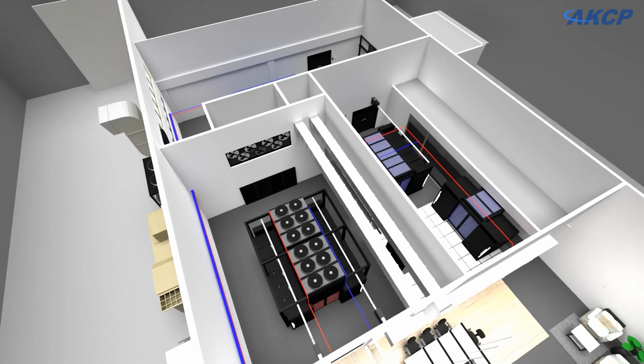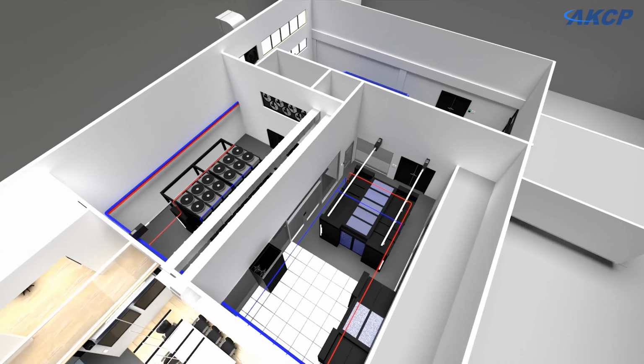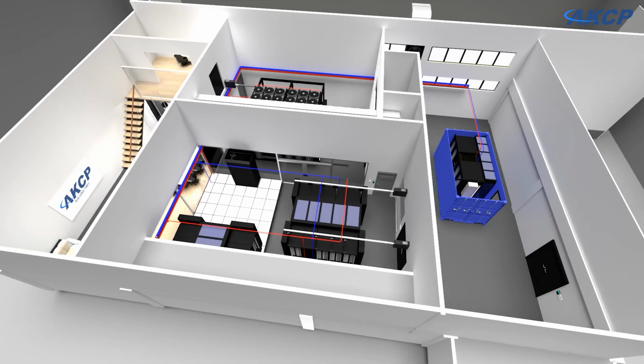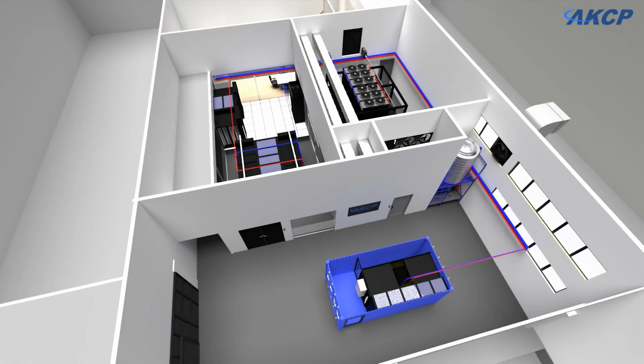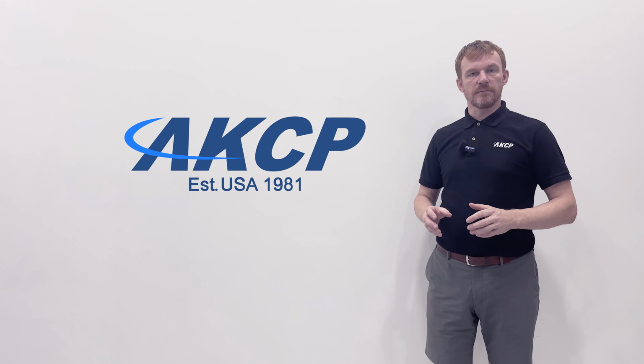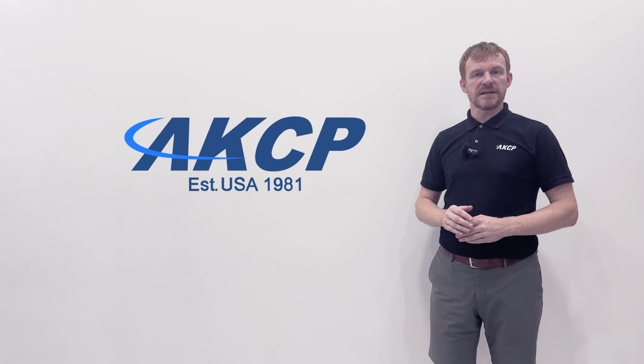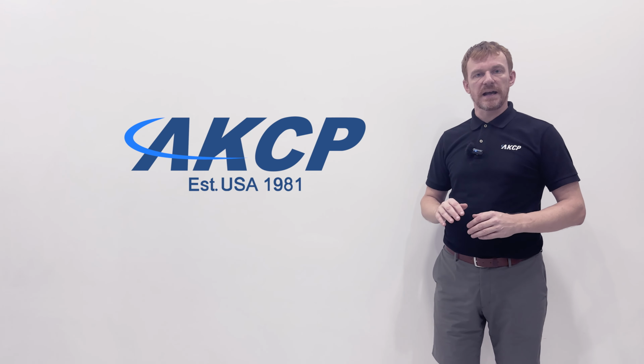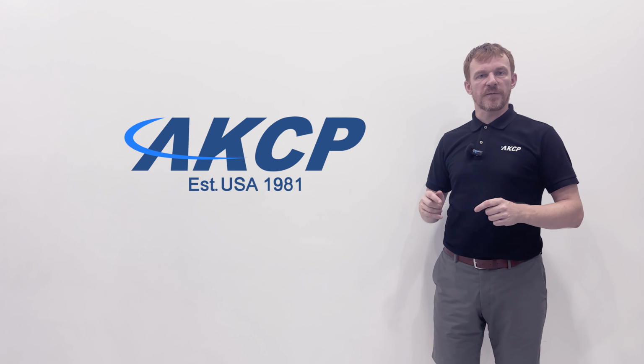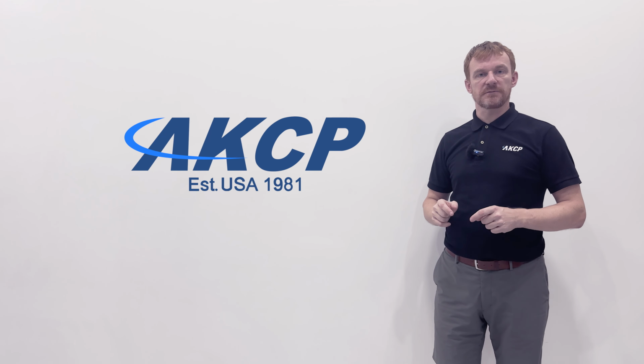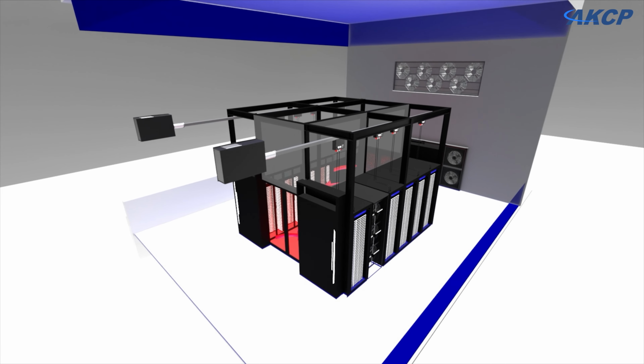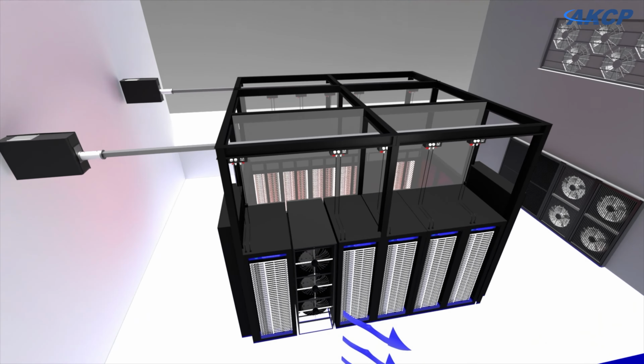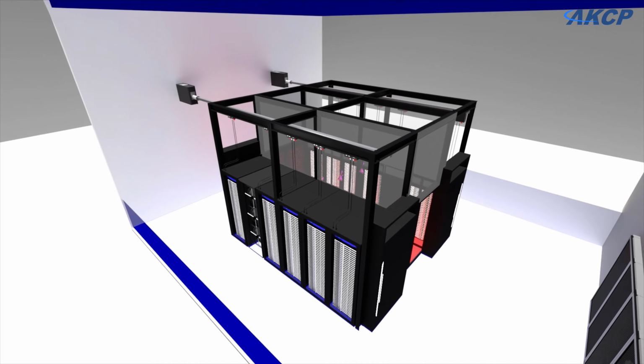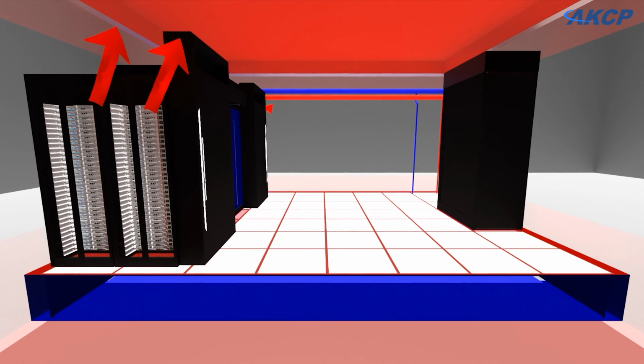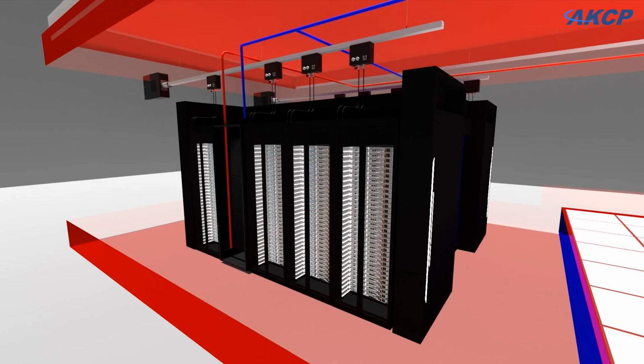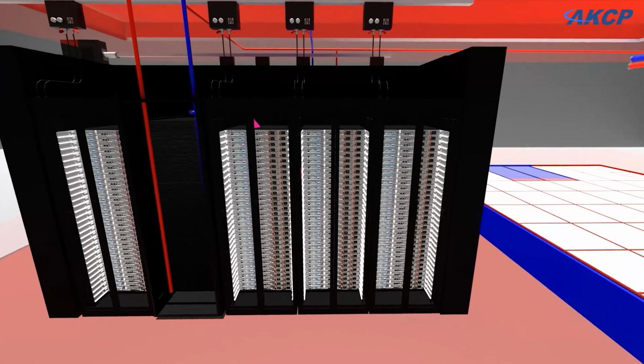What you can see on the screen is our 3D representation of the test data center under construction. We've got hot aisle containment, cold aisle containment, fan walls, and at the moment we're doing construction of a steel structure to support our overhead rooftop heat exchangers. We have a few videos going into more detail on this, check the link in the description. In addition to the hot aisle containment with rooftop heat exchangers, we'll also have in-row AHUs and the fan wall. In the cold aisle containment area, we have a raised access floor and in-row AHUs also.